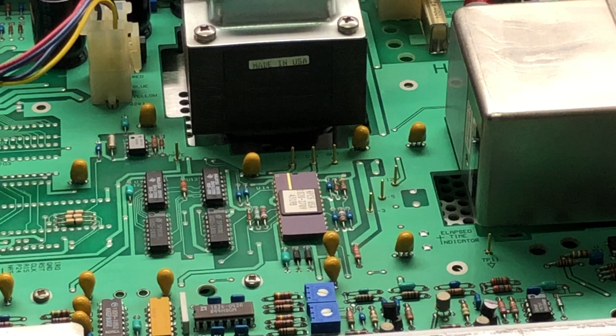Now again, there's only one adjustment for the power supply in the whole instrument. The other voltages are fixed, so either they work or they don't. If they're out of spec, there's a component that would be faulty. The 3 volt has an adjustment, and the specification in the service manual calls for 3.00 volts plus or minus 0.02 volts. So we'll look for that accuracy and see if that 3 volt supply is within specification. If it's not, we can make an adjustment on that.